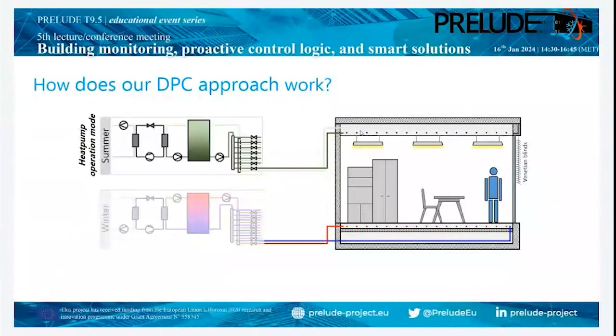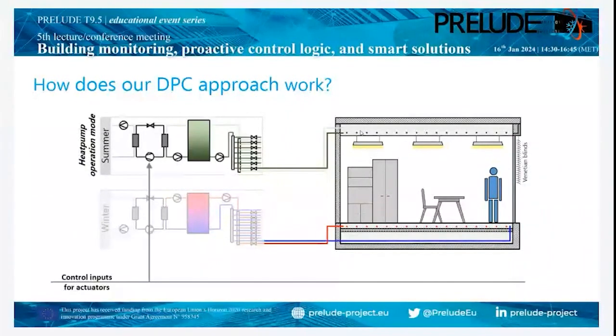In the summer operation mode, the reversible heat pump can also load up our cold water storage tank, and we need the near surface cooling system in the building to cool down the rooms. So we can also use the control inputs for the near cooling surfaces, so the cooling power, to cool down the rooms, and we can also reduce the solar loads in the thermal zones by increasing the shading height of the Venetian blinds, for example. If we do that, we have a reduction of the solar loads, and maybe through that we can also reduce the energy demand for cooling.